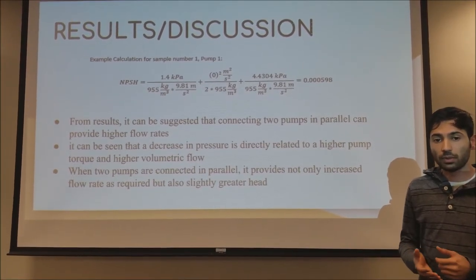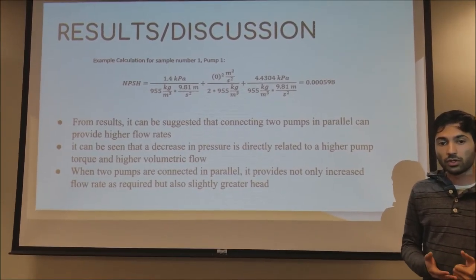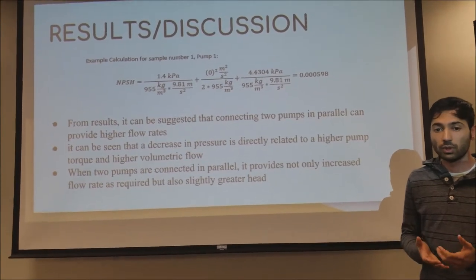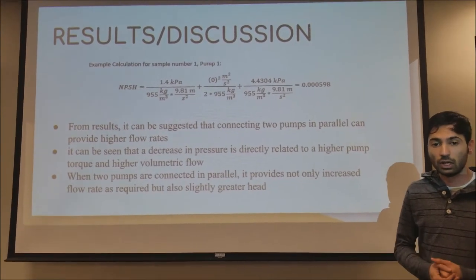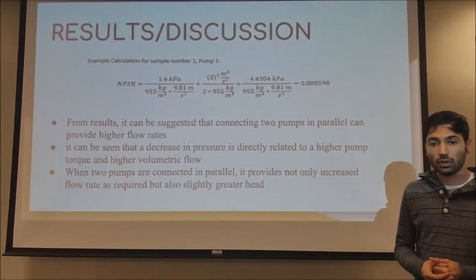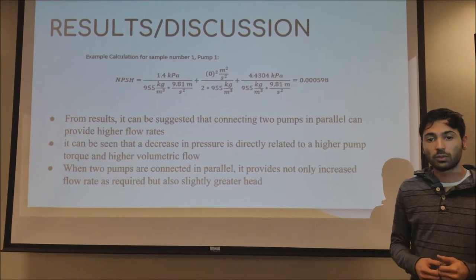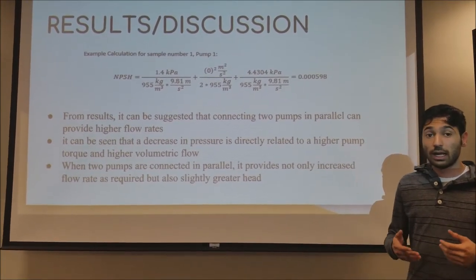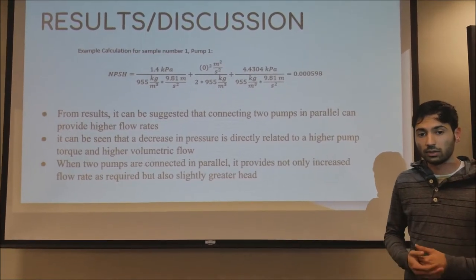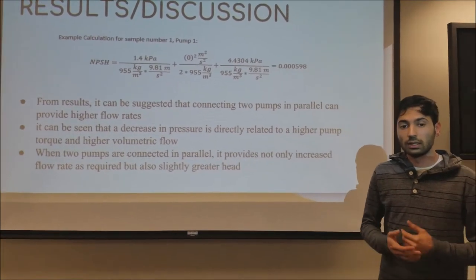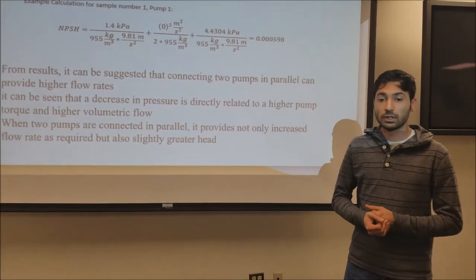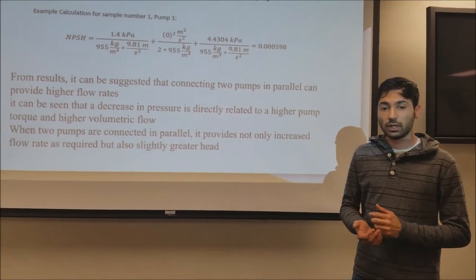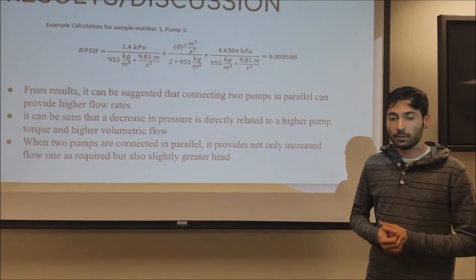At higher pump RPMs, the outlet pressure is higher, whereas the inlet head pressure remains relatively consistent. This relationship is why the output heads are higher for higher pump RPMs and is expected to behave this way. The effective two-pump performance curve is obtained by adding the flow rates of each pump at the same head.